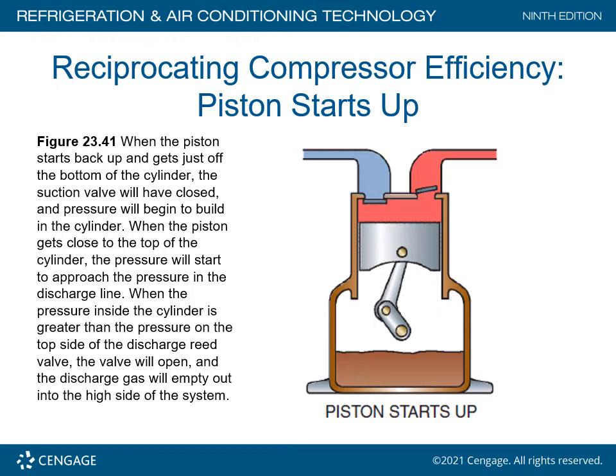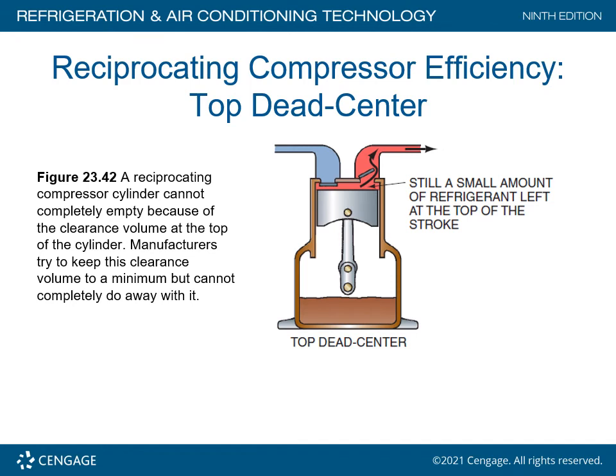Reed valve construction — I've also seen these break. On most serviceable or semi-hermetic units, valve plates are the weak link. At top dead center (TDC), a reciprocating compressor cylinder cannot completely empty because of the clearance volume at the top of the cylinder. Manufacturers try to keep this clearance volume to a minimum but cannot completely eliminate it — there is still a small amount of refrigerant left at the top of the stroke.